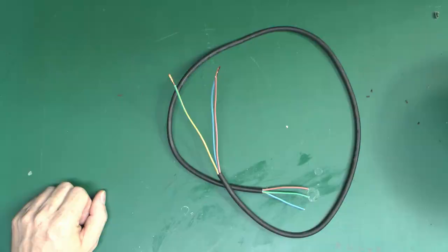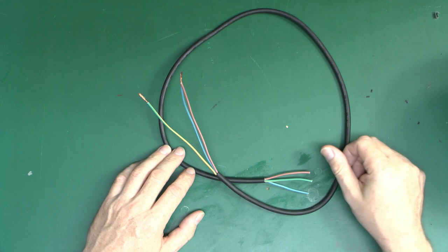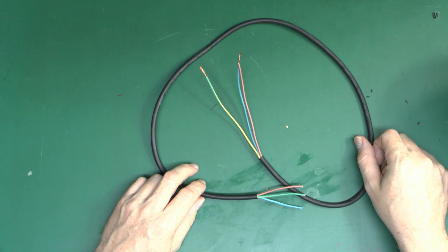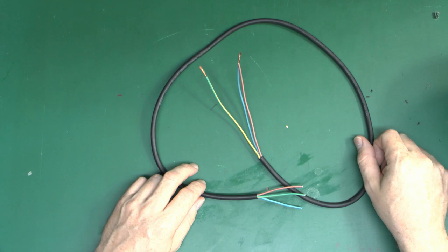There was a number of other faults elsewhere with junction boxes underground being full of water and so on. But this cable turns out to be one of the faults, so let's just have a quick test of this and see what kind of results we're getting. So this is the bit of flex we've got. These particular lights were the spike variety. Had about a meter or so of flex attached to them. And the ends of it, which I've also cut off here, went into some junction boxes which unfortunately being buried partly in the flower beds were mostly full of water, and there's faults and problems there. But it turns out that this cable itself, or this flex, is also somewhat faulty.